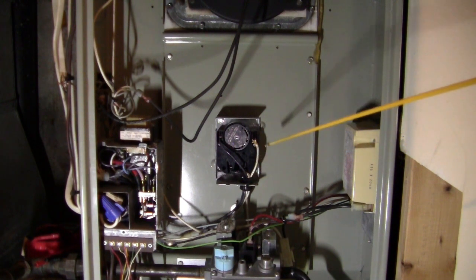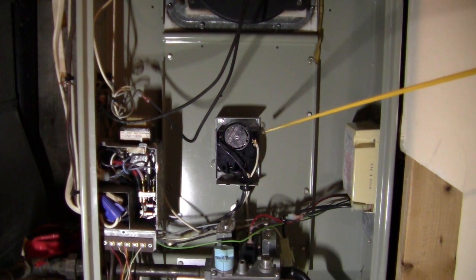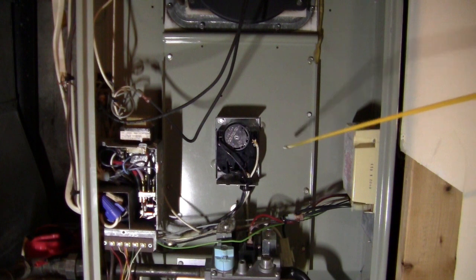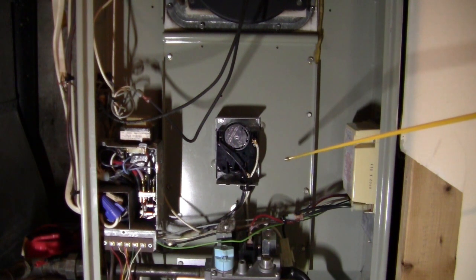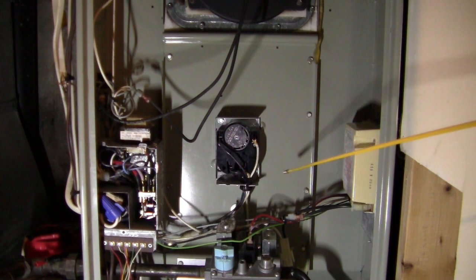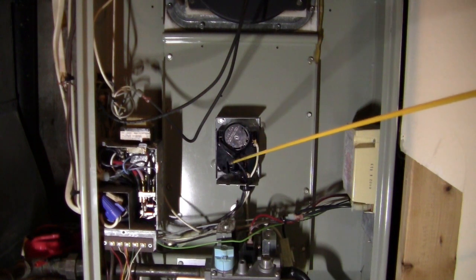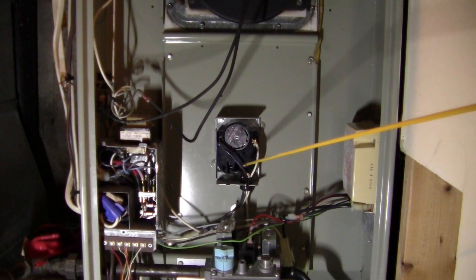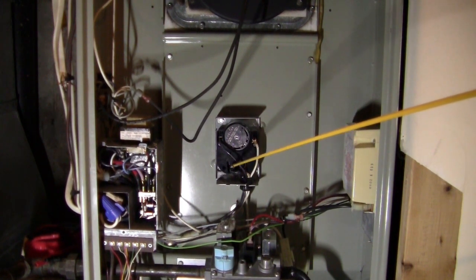Some are defined to reset after the unit cools down for some time. But be careful. Once this happens, cut off your unit. Don't just come over here and switch it on. If you switch it on, sometimes you haven't found the cause, and it might kill your gas again. It can stop working again.